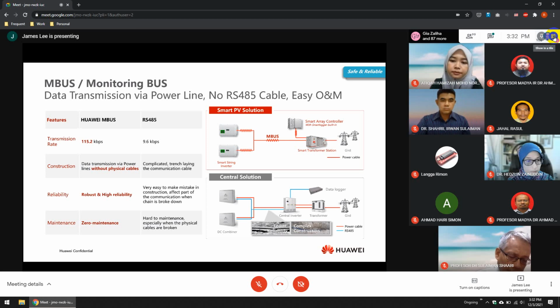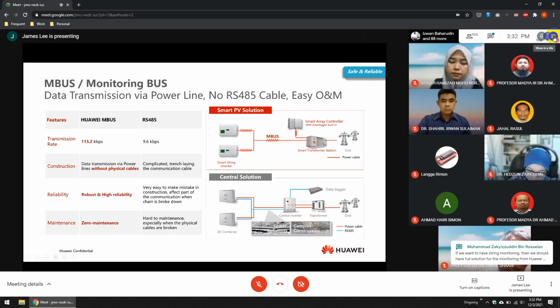Because of this MBUS capability, which we've had from day one implementing for solar farms, the transference rate is very high. More importantly, it's transferred to nodal points where the transformer stations are, so it's only negotiating with a limited number of inverters at a time - currently 32 inverters. So our ability to respond to the grid is in milliseconds, well above the requirements of the grid utility companies. We have zero maintenance, and it's more robust and reliable.